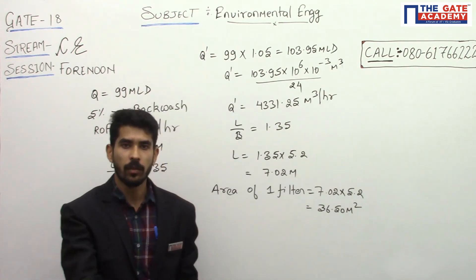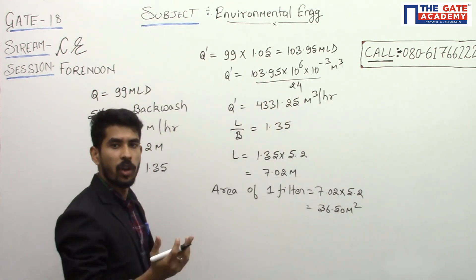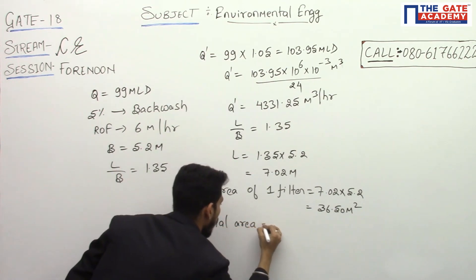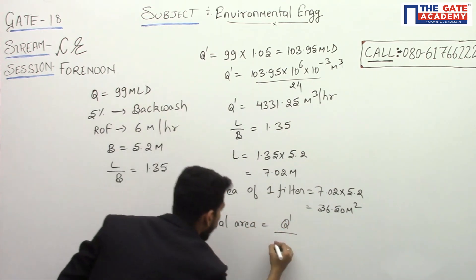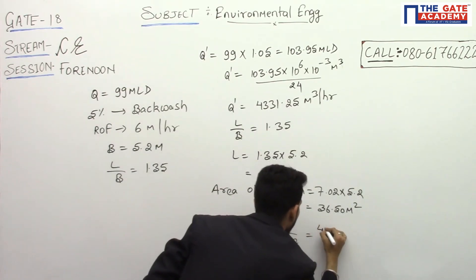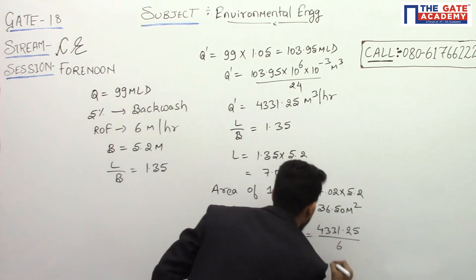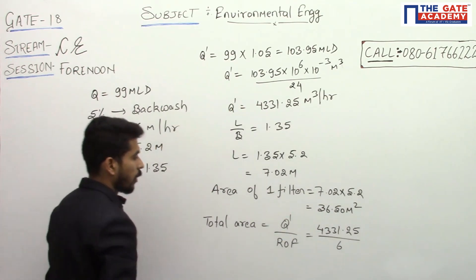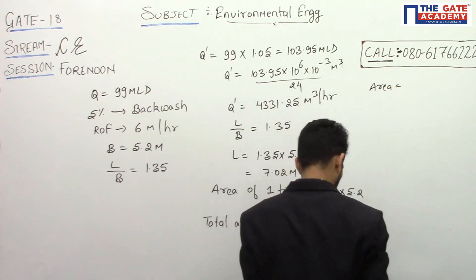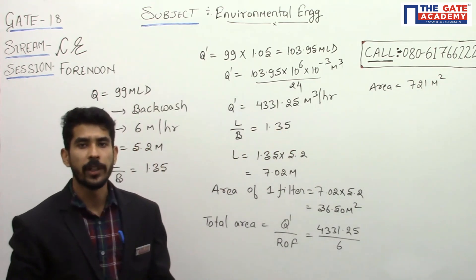Now let us find what total area is required. Total area equals Q effective divided by the rate of filtration. That is 4331.25 divided by 6, which gives a total area of 721 square meters.